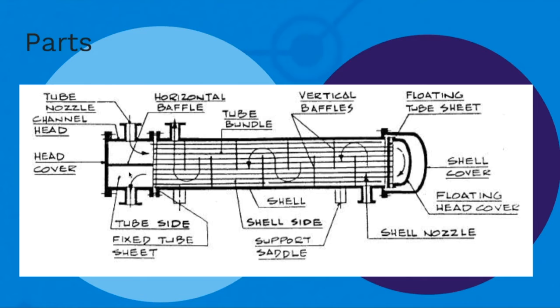The outside material is the shell. The inside material is in the tubes. There are vertical and horizontal baffles, support saddles on the outside to prevent bending or breaking, and a shell cover. Typically they're also covered with insulation material to control heat transfer to the ambient environment.